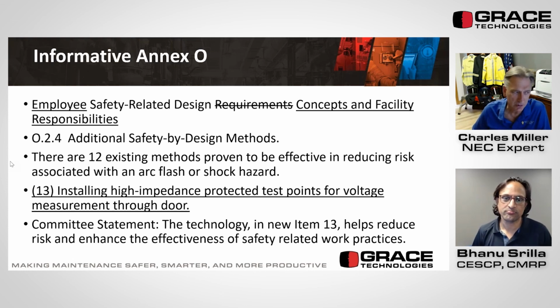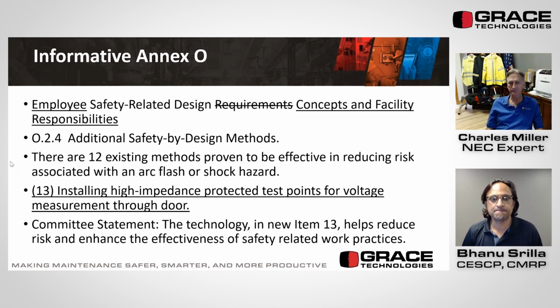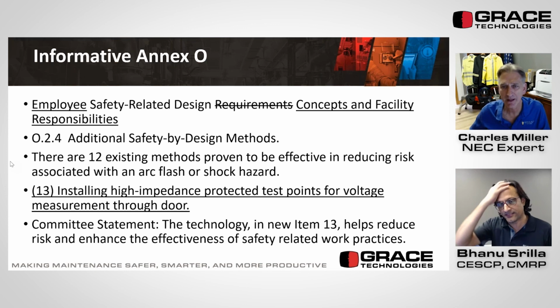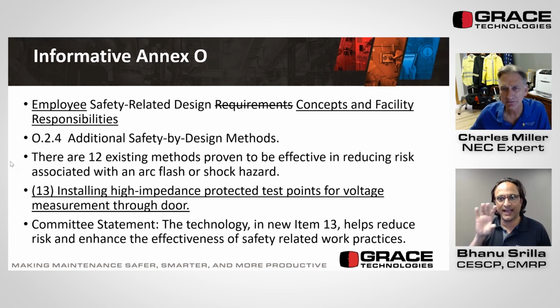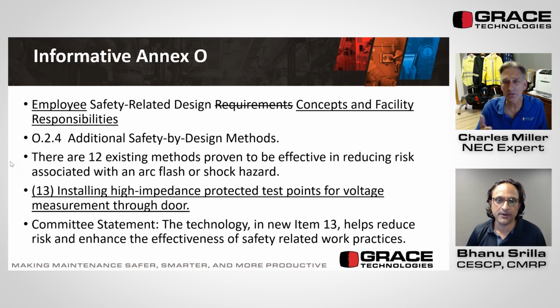To do what? Okay, repeat what you were asking, Bhanu. So my question is, basically, if somebody has a label, an arc flash label, that clearly calls out the available fault current, would that meet the requirement of the new proposed text of having equipment rated for available fault current in the normal operating condition?